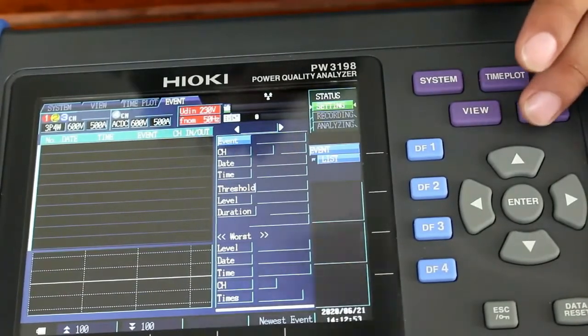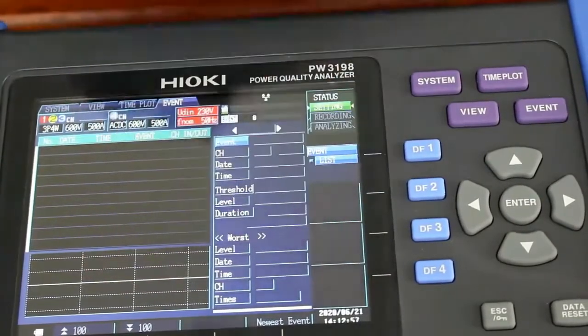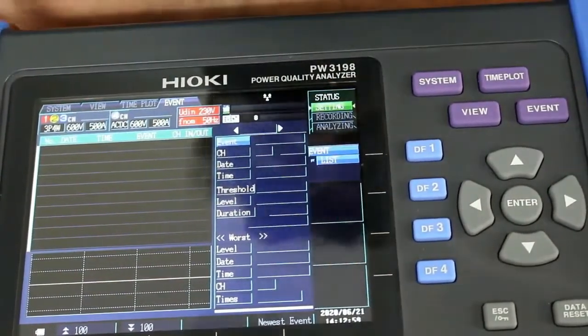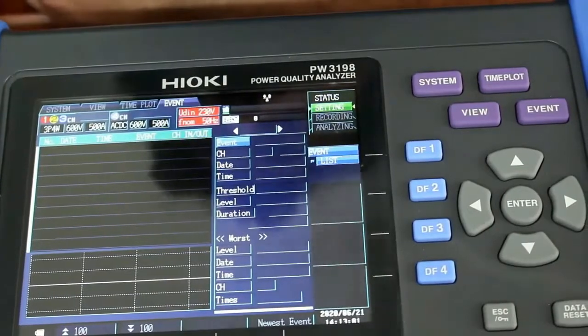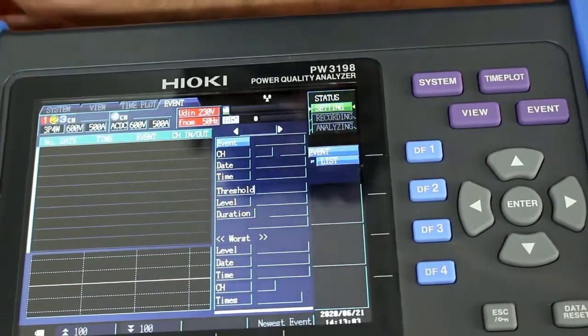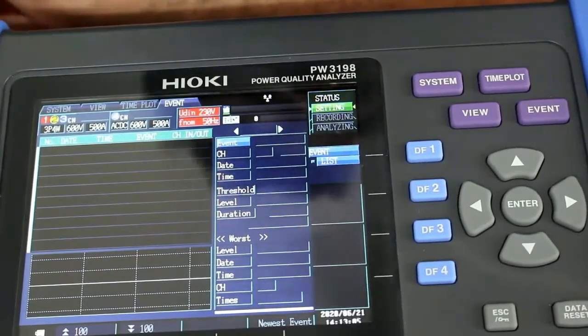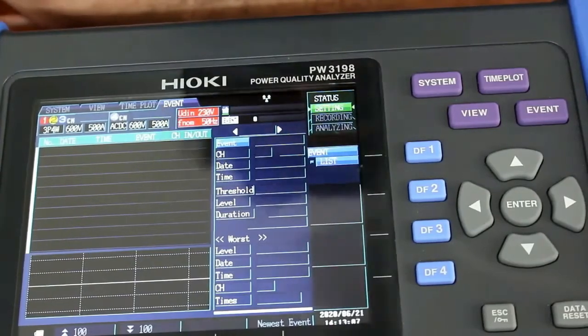When I press event, all the data comes up here. I can scroll up and down to see all the parameters like anomalies - sags, dips, interruptions, transients - whatever is there per the IEC standard, it can measure all those parameters.